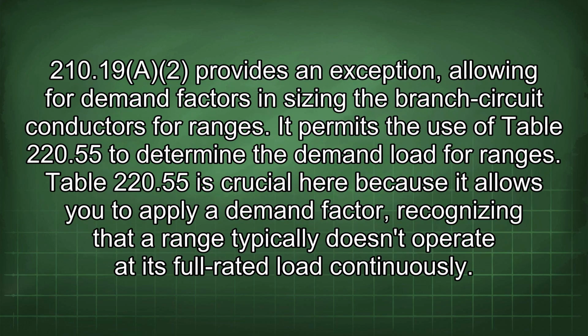210.19 A 2 provides an exception, allowing for demand factors in sizing the branch circuit conductors for ranges. It permits the use of Table 220.55 to determine the demand load for ranges. Table 220.55 is crucial here because it allows you to apply a demand factor, recognizing that a range typically doesn't operate at its full rated load continuously.